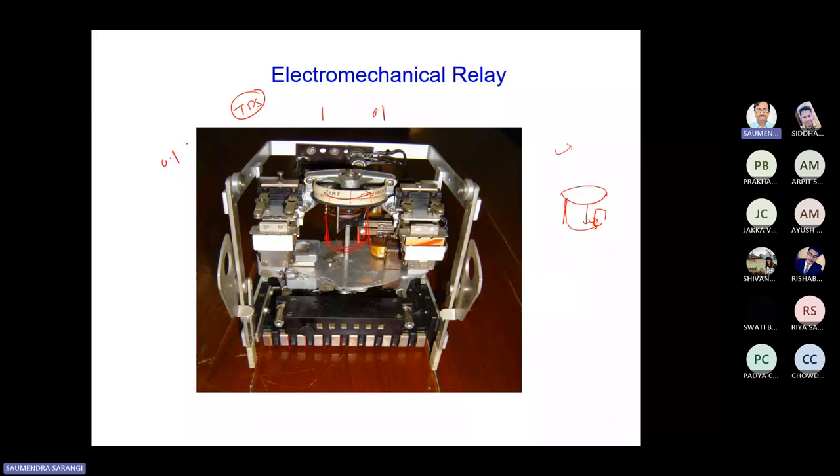If it is towards the load point, that may be kept as 0.1. However, the other relays should be having minimum time of operation. In the case of DMT, whenever the fault current increases, the definite minimum time, it should wait up to this much time and it should operate, right?